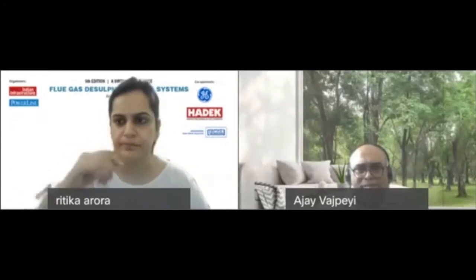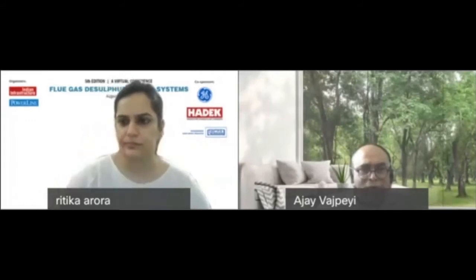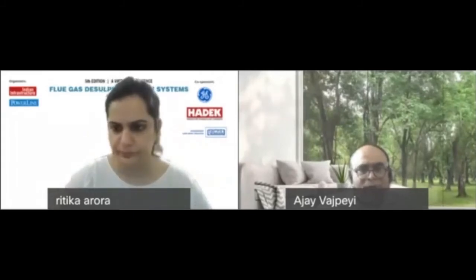What is the approximate compressed air requirement for wet FGD in a 600 megawatt thermal power plant? You don't really need any regular requirement of compressed air for a wet FGD system. Some amount is needed for pneumatic actuators which you might have in the plant, or for fabric filters as far as dedusting systems are concerned. So technically, on a regular basis, there is no regular requirement of compressed air for the plant.